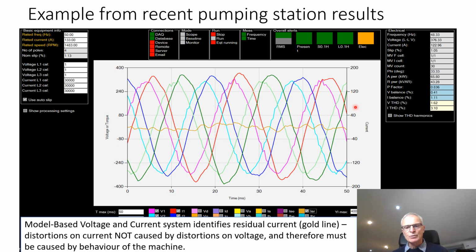The system's done that automatically, and it's showing up here the overall, these four boxes here. This first one shows you the overall condition of the machine at the moment, and it's green. The next one is the predicted short-term condition, which means up to a month from now, that's green. The predicted long-term condition means up to 3 months from now, and that's green. And the fourth box indicates an issue with the electrical supply, and we'll look at that in a minute.